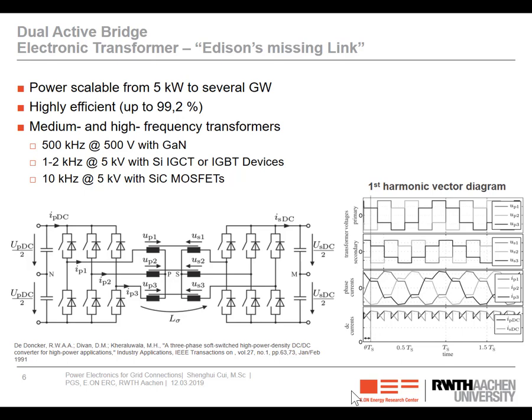So here I would like to briefly introduce the basic operation principle. As you can see here, the two bridges are operating in the so-called block mode, so that all the switches are operating at a 50% duty ratio. And if you look at the phase voltage, it is actually in the form of a 6-step voltage. When we want power transfer to occur, we just need to apply a phase shift, the so-called phase shift load angle, between the primary side and the secondary side. Then we can have such a transformer current which is delivering power.